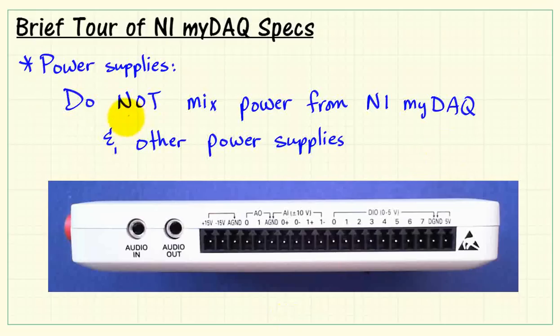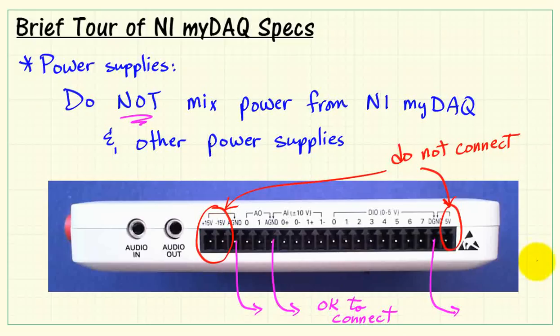Do not mix power from NI myDAQ and other power supplies. If you're connecting myDAQ to other circuits and systems that have their own power supply, you will need to establish connections between the grounds of myDAQ and the other system. But when you do so, do not connect the plus-minus 15 volts and 5 volt outputs from myDAQ.